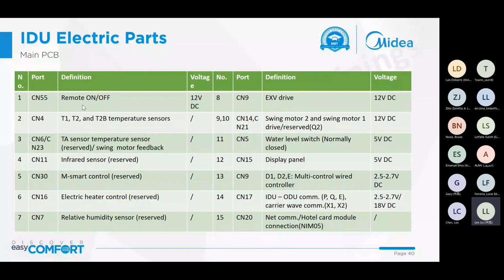This is the specification of the ports of the indoor PCB. We can see different ports with different functions. Usually it's 12 voltage, 5 voltage, and 3 voltage. For remote on-off, EXV, and swing motor for cassette and high wall it is 12 voltage DC, and the 5 voltage is for the water level switch and display panel, and 3 voltage is used for wired controller communication.